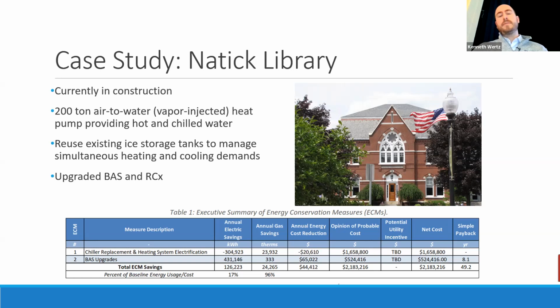And one sort of advantage they had that not a lot of buildings are going to have is that they had ice storage tanks in the basement that were originally designed to let the chiller run at night as opposed to during the day when electricity was cheaper. The rate structures changed a little bit, so they weren't making full use of it. But the nice thing with the heat pump is if you've got a heat pump that can make chilled water or hot water, but during the day you need both, you can use the ice storage to make chilled water at night and then make hot water during the day. And you can satisfy your building all 24 hours, even though the system itself isn't capable of doing it at any given time.